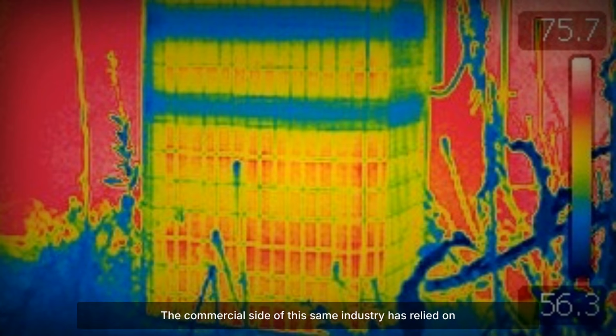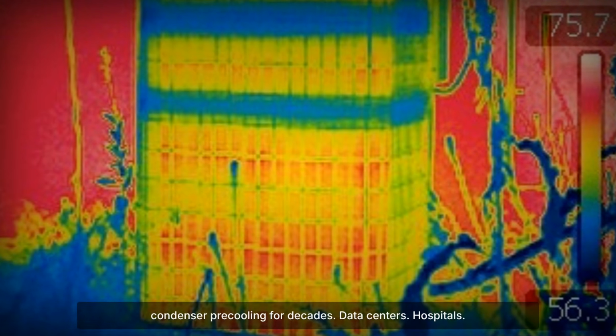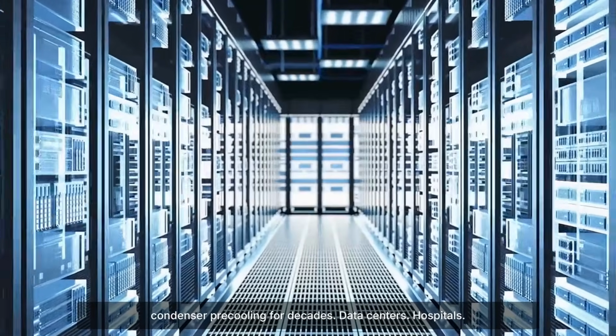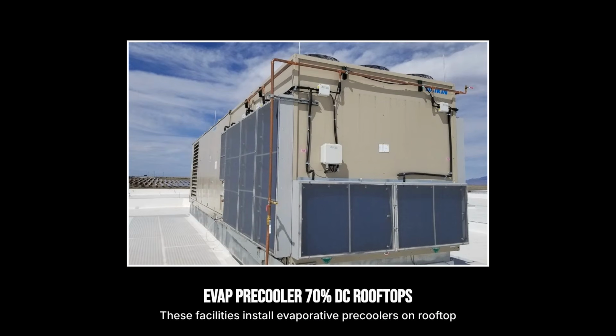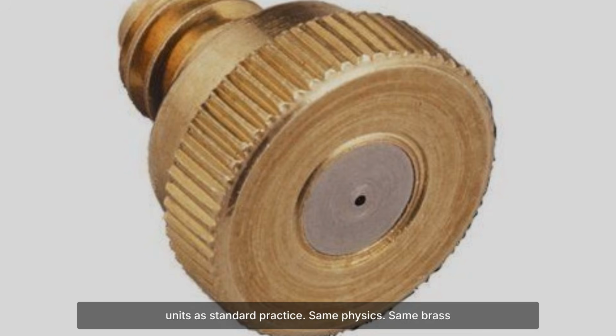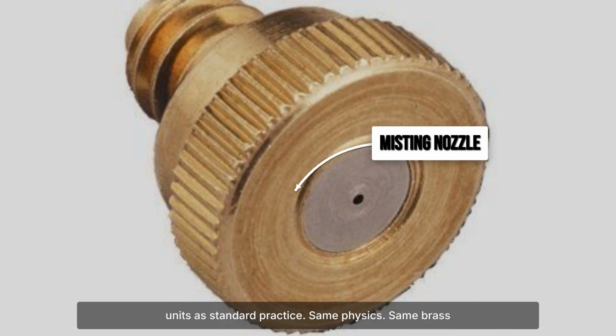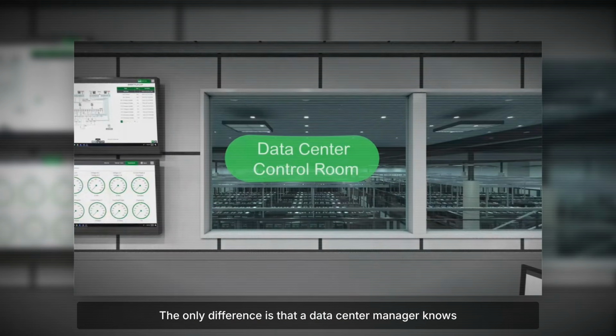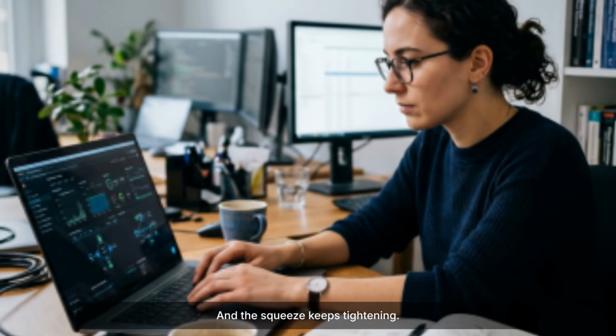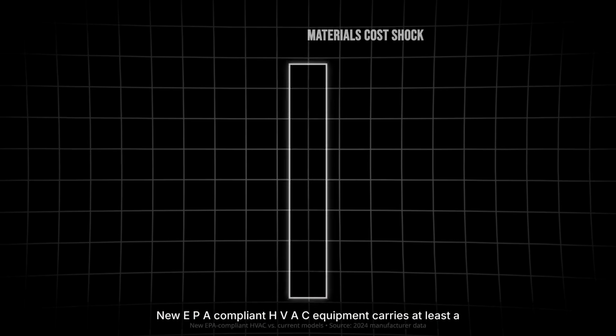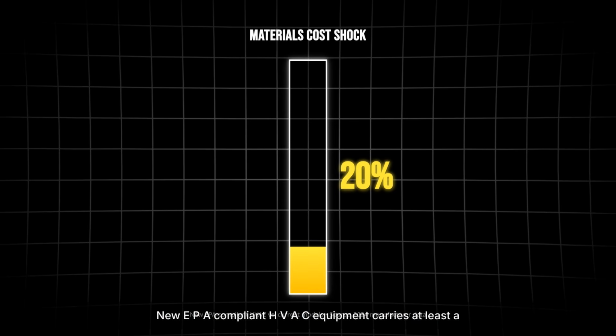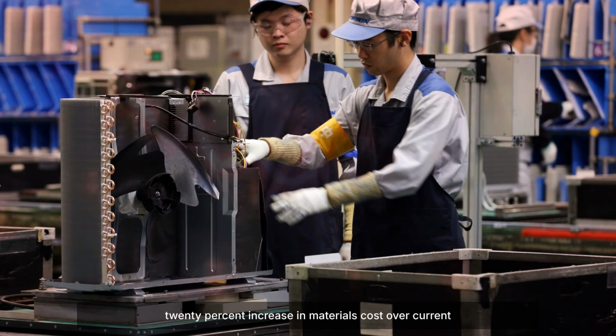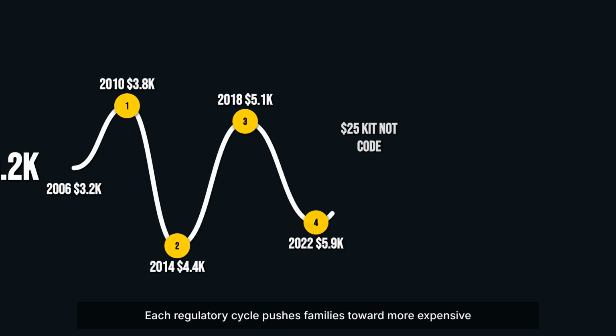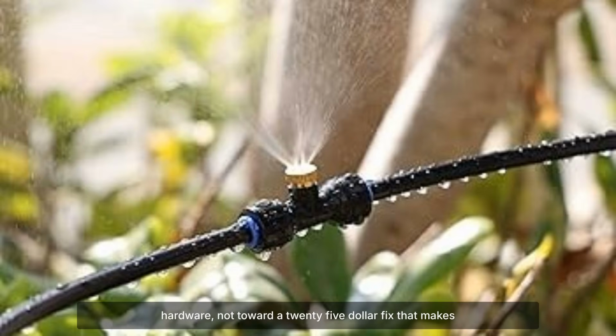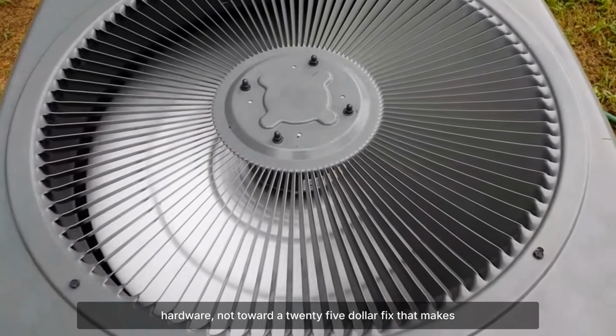The commercial side of this same industry has relied on condenser pre-cooling for decades. Data centers, hospitals, big box retail, these facilities install evaporative pre-coolers on rooftop units as standard practice. Same physics, same brass nozzles. The only difference is that a data center manager knows about it and you do not. And the squeeze keeps tightening. New EPA compliant HVAC equipment carries at least a 20% increase in materials cost over current models. Each regulatory cycle pushes families toward more expensive hardware, not toward a $25 fix that makes existing hardware perform 2 efficiency tiers higher.